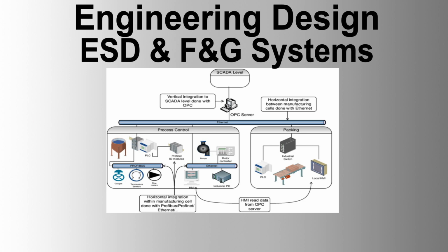Testing and commissioning. 1. Factory acceptance testing, FAT. Comprehensive FAT must be conducted to validate the system's performance before delivery. FAT procedures should include functional testing, performance testing, and integration testing. 2. Site acceptance testing, SAT. SAT must be performed after installation to ensure the system functions correctly in the operational environment. SAT procedures should include point-to-point checks, system functionality tests, and validation against design specifications.